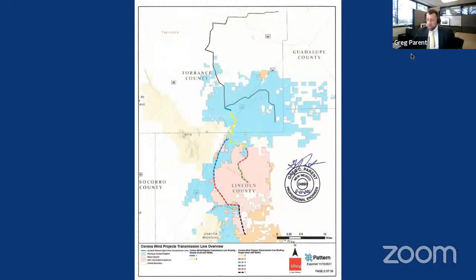As I said previously, where the color of the different segments, both solid and dashed, changes color, that location is a collection substation, where a lot of the turbines' power is brought and the voltage bumps up to a higher voltage. If all of these collection substations were in one line, we would probably do a double circuit system, but the substations are spread all over. There was only about 10.5 miles where we could bring those two lines together into one route, and that's where we chose to do the double circuit line. The rest, we had to separate the two circuits to pick up the substations, which are spread further apart.